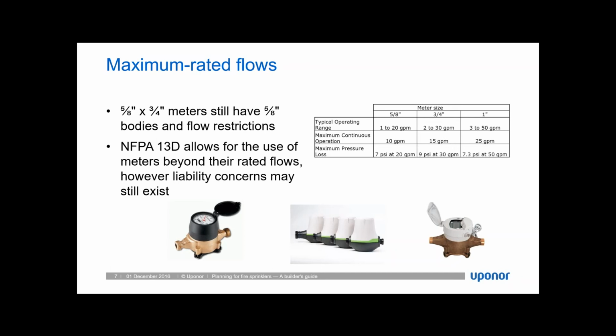Now, this may be true, but there are also going to be some risks involved in continuing with the use of a 5/8 meter on a sprinkler system that requires a flow higher than its maximum rating. One option is to use low-flow sprinkler heads, which can flow as little as 10 gallons per minute, and then our demand of the most remote 2 sprinklers would be a total of 20 gallons per minute, which obviously is within that maximum range. This is definitely a good solution. However, low-flow sprinklers have restrictions on spacing. They cannot be spaced as far apart as the standard residential sprinklers. You are often limited to 14 by 14, where you can have 16 by 16 spacing, or even 18 by 18 when using standard residential sprinklers.